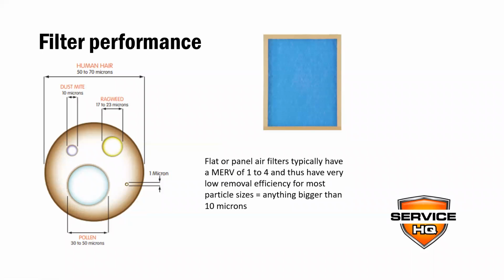Now, a flat or panel air filter typically has a MERV rating of 1 to 4. MERV is a unit of measurement that scientists have come up with to decide how much particulate matter a filter can remove from the air. So 1 to 4: the higher the MERV rating, the more it filters, the more particulate matter it removes from the air. These flat panel filters are not very good, and we see these all the time. They only have a MERV rating of 1 to 4.